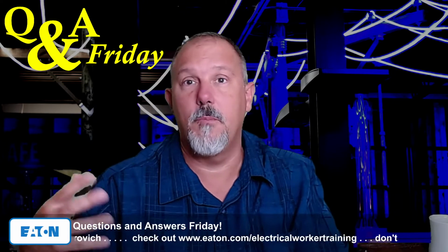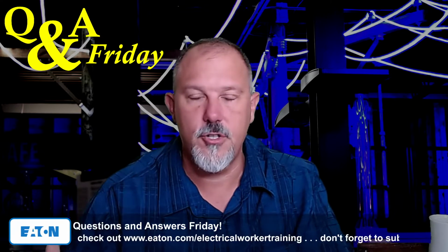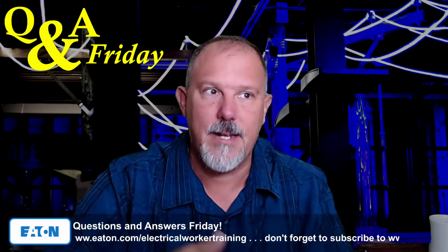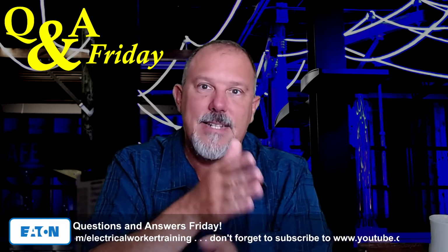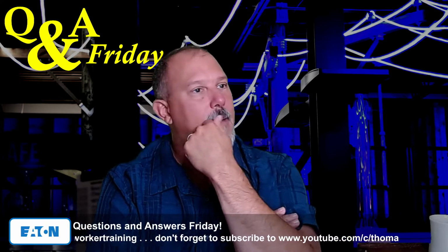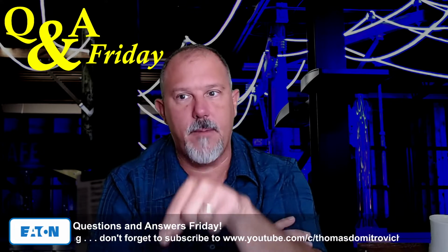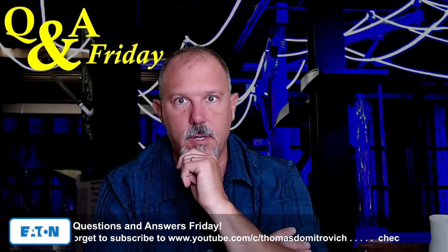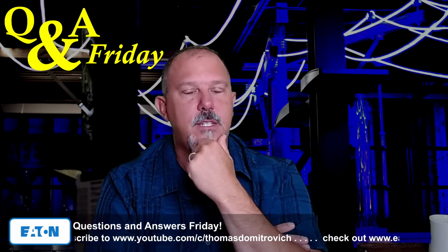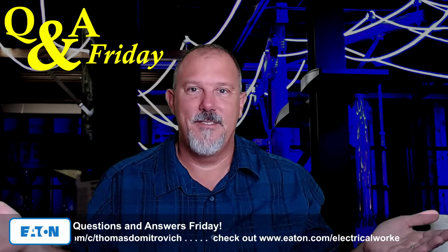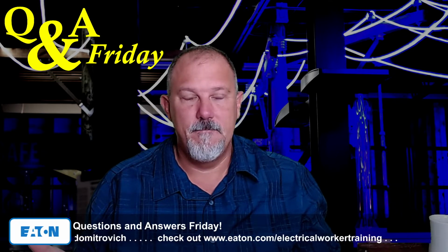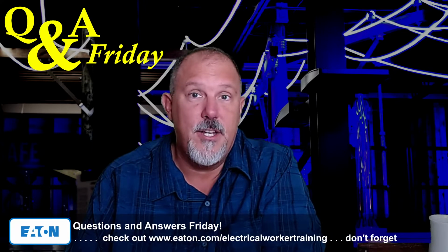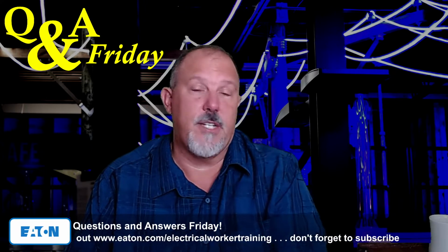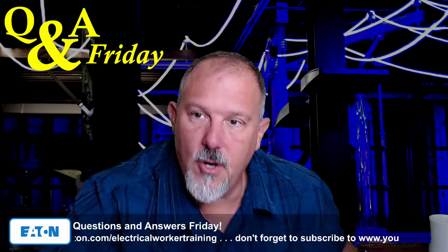But if I use a larger breaker, it's larger lugs, there's larger everything in there, and I put a smaller conductor on it, and as long as I'm protecting that conductor at its ampacity, I can't perceive the problem right now, but I'll do my homework and make sure that that's correct. But I wouldn't call it a 100% rated application either, right? Because it's not a 100% rated breaker that you need. You have a larger breaker than what you need, and you're adjusting it down. I will do my homework on that one, John. Good question, though. Good question.